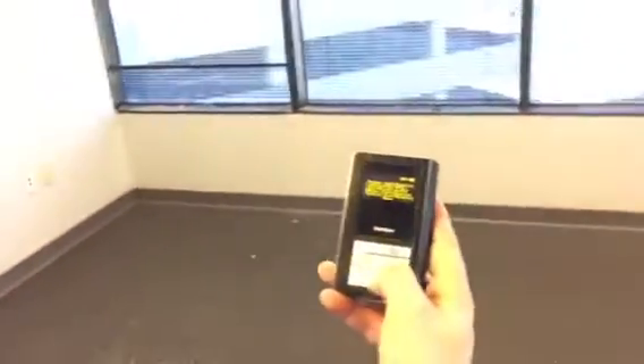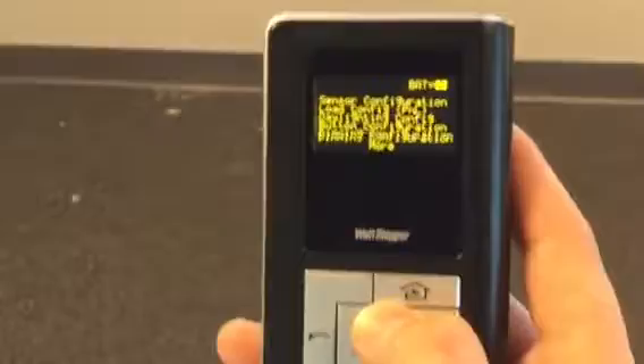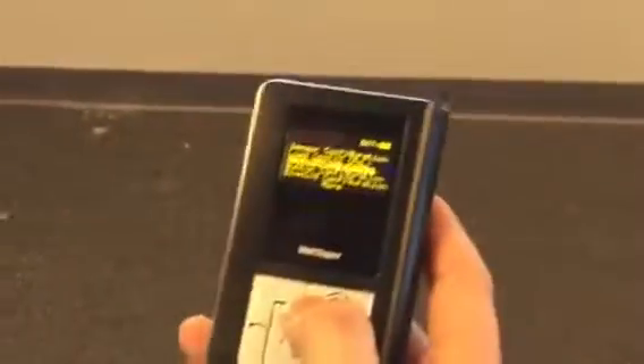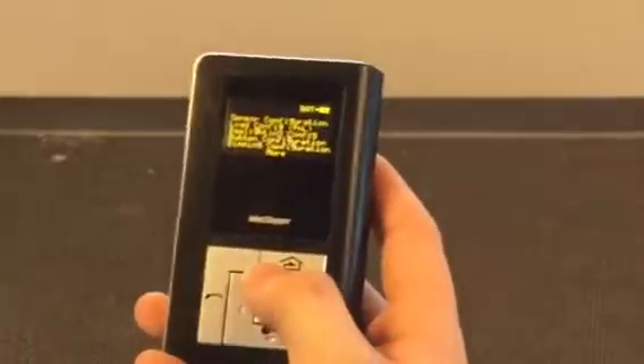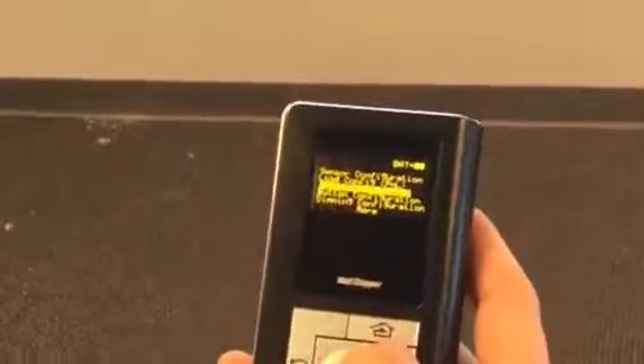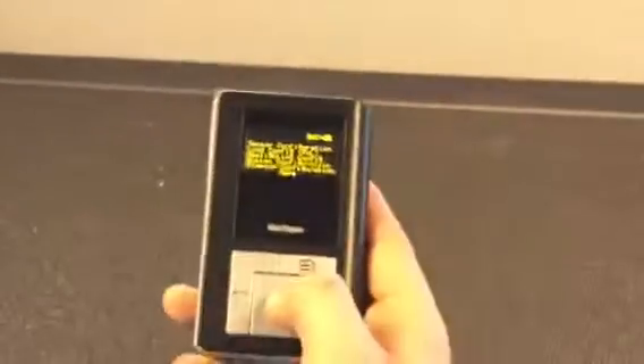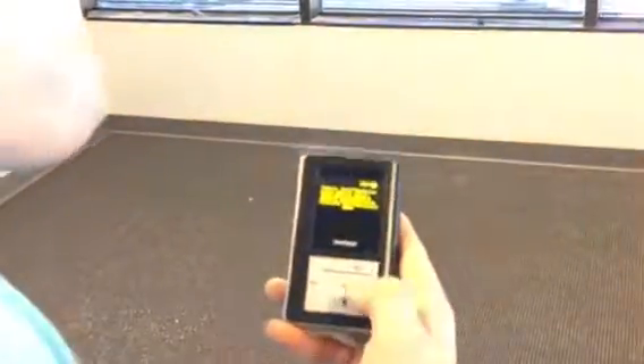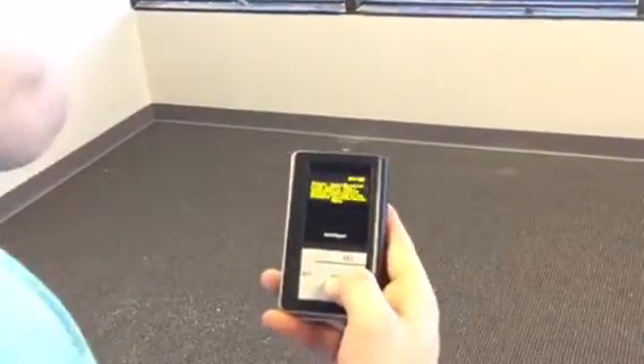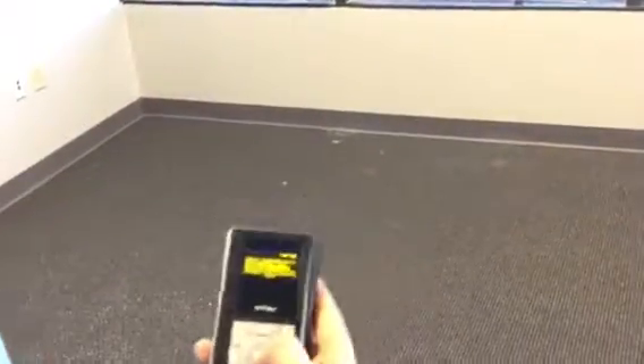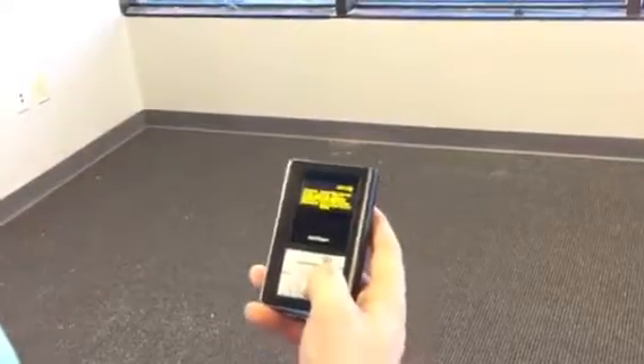Next thing we want to do is configure the daylighting sensor. In a standard operation, you want as much light coming in as you can when configuring daylighting. If you're dealing with an LS500, it must see at least 10-foot candles or the calibration will fail every time. If you're doing an LS500, it requires a light meter, as you're going to have to tell it what levels you see. An LS400, like we have on this job, is self-sustaining, auto-calibration. It's going to turn lights on and off, and it's going to do its thing.